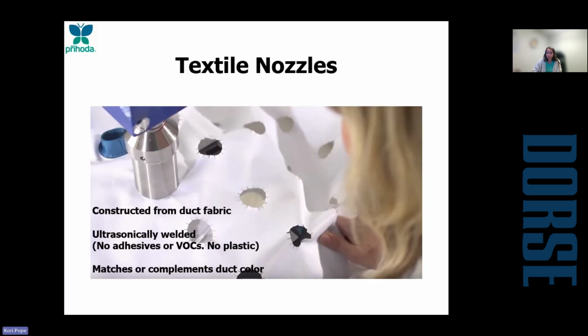And that leads us into our textile nozzles. So whenever we need to get the air moving further than the 40 feet, we're going to jump up to our textile nozzles. All of our nozzles are constructed from the same fabric that our ducts are, and they're also ultrasonically welded on to our duct, whereas other manufacturers maybe use a two-piece press fit plastic nozzle, or they're Velcroed on or anything like that. So you don't have to worry about the nozzles coming off regardless of the application.